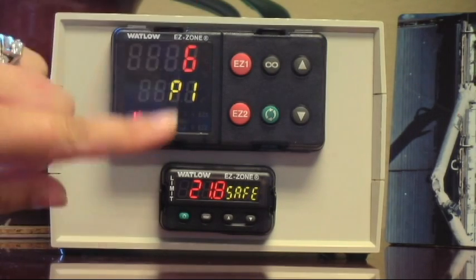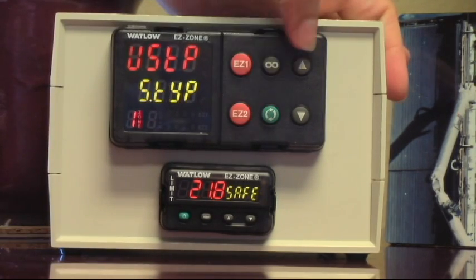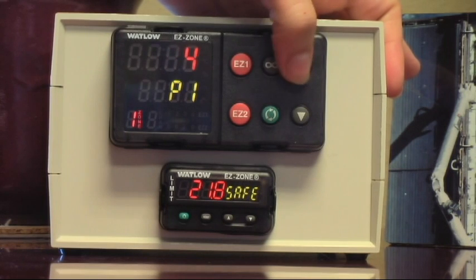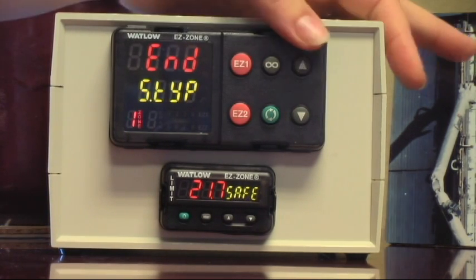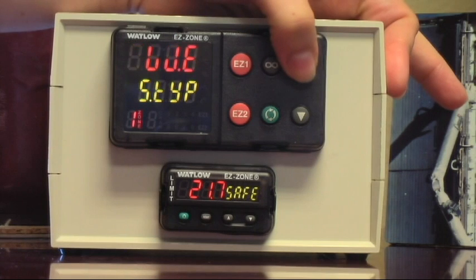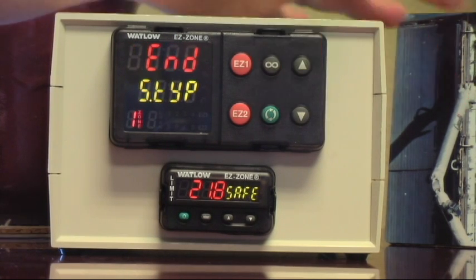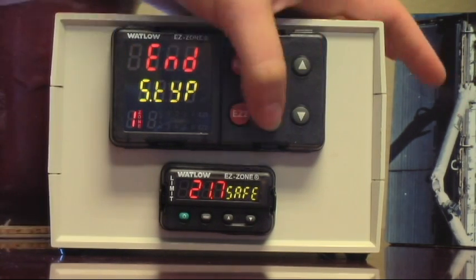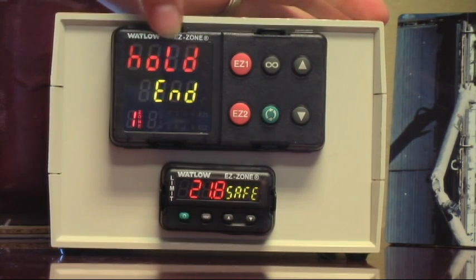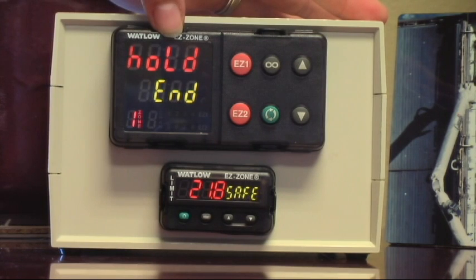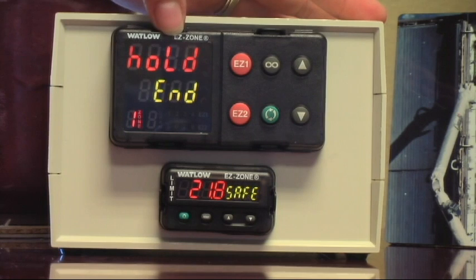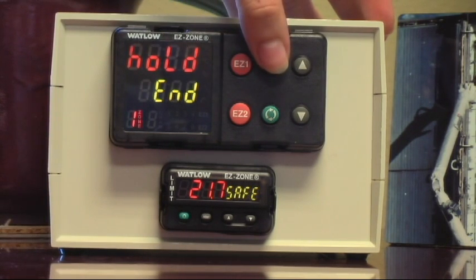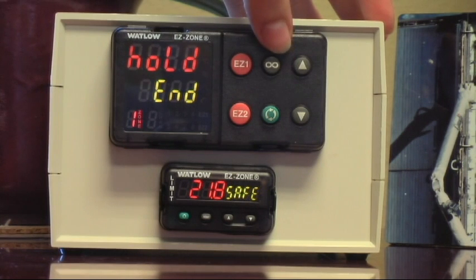So step five, green key. Oopsies, I did it again. Step five, green key. And we're going to select end. So you just go through all these just so that. There's end. The end set point. Green key. And remember, we're going to select hold because our last step was a time down to ambient. So now we're going to say, just hold the ambient and you're done. Okay. Okay. We set everything.